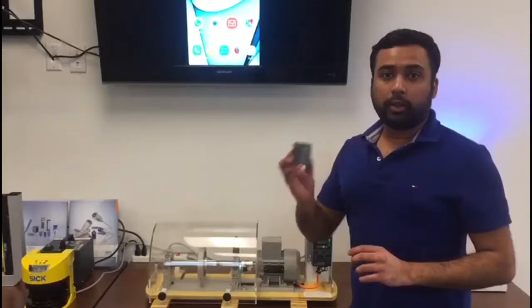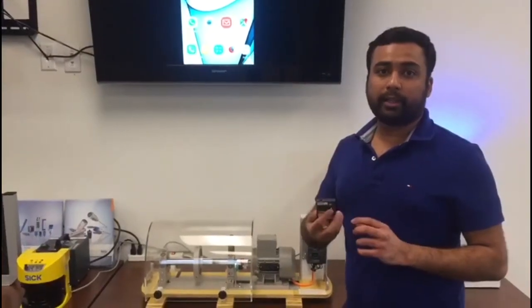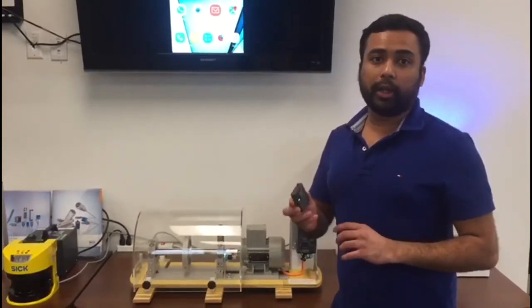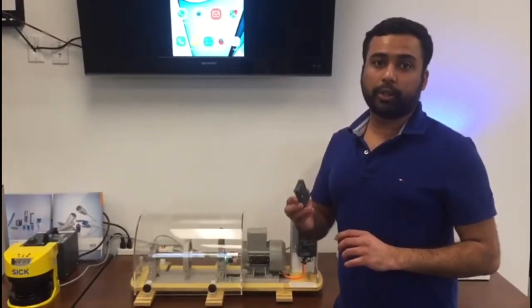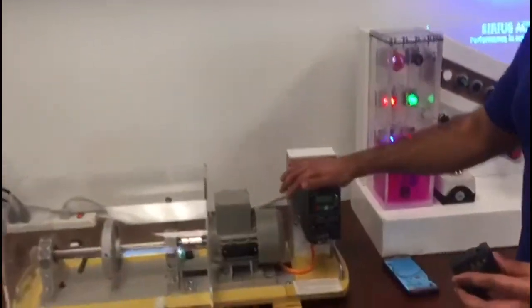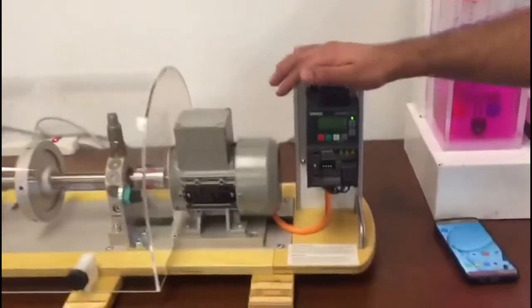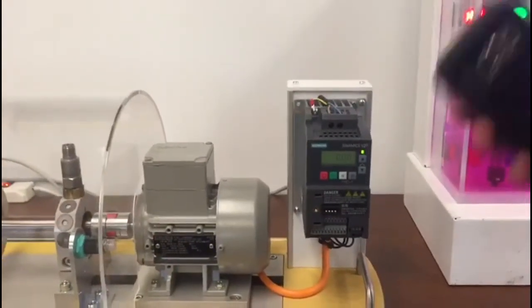Let's get started. Today I'm going to show you the Smart Access module for the V20 drive. It's a Wi-Fi add-on card that enables a wireless hotspot to your V20 drive so that you don't need a cable to commission or communicate with the drive. You can simply use your phone's Wi-Fi. It's pretty nice.